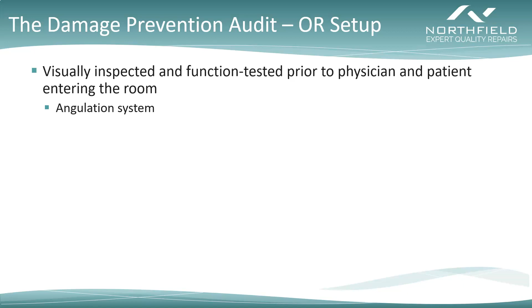We're going to start in the OR setup. First, we want the device to be visually inspected and function tested prior to the physician and the patient entering the room. Now, some simple tests that can be performed are on the angulation system, and we want to look for those early signs of damage. And again, we're talking about play in the knobs, which means that when you turn the knob, the distal tip isn't quite as responsive as it needs to be.